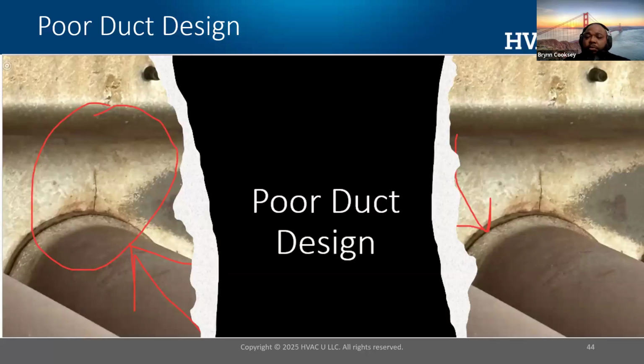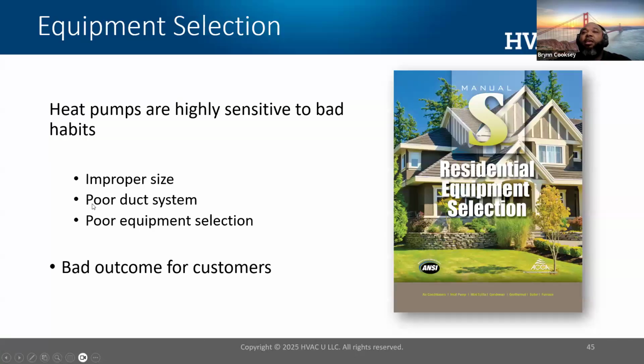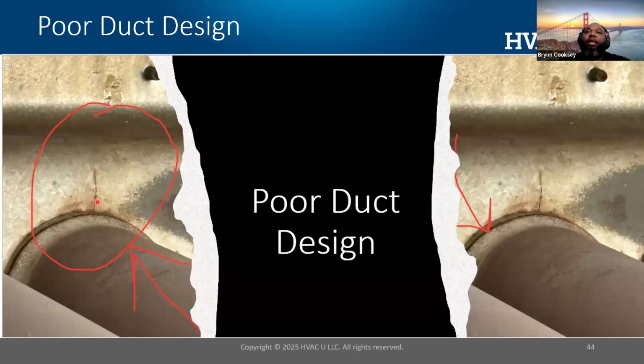Airflow is so prevalent in our contracting business, we linked it to critical failures like heat exchanger failures. What you're seeing now is a forced air furnace system, and this is a crack right inside this apparatus, or heat exchanger, where the exhaust gases go through our furnace and up and out to the atmosphere. Due to poor duct design, this heat exchanger has failed. If I look here at this heat exchanger, this crack will allow exhaust gases to get into the people space. This was caused by inadequate airflow or improper duct design for our heating equipment.